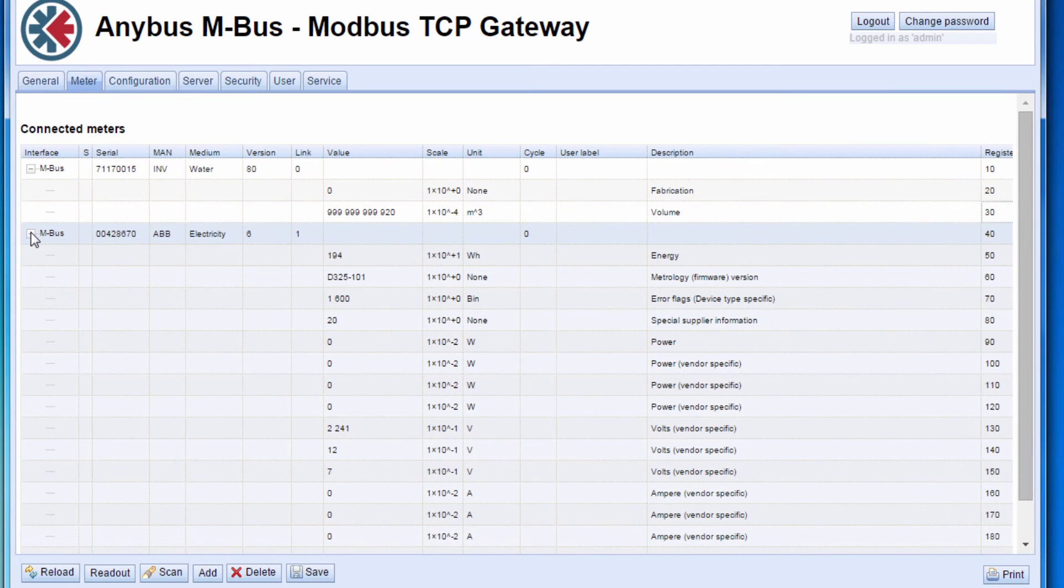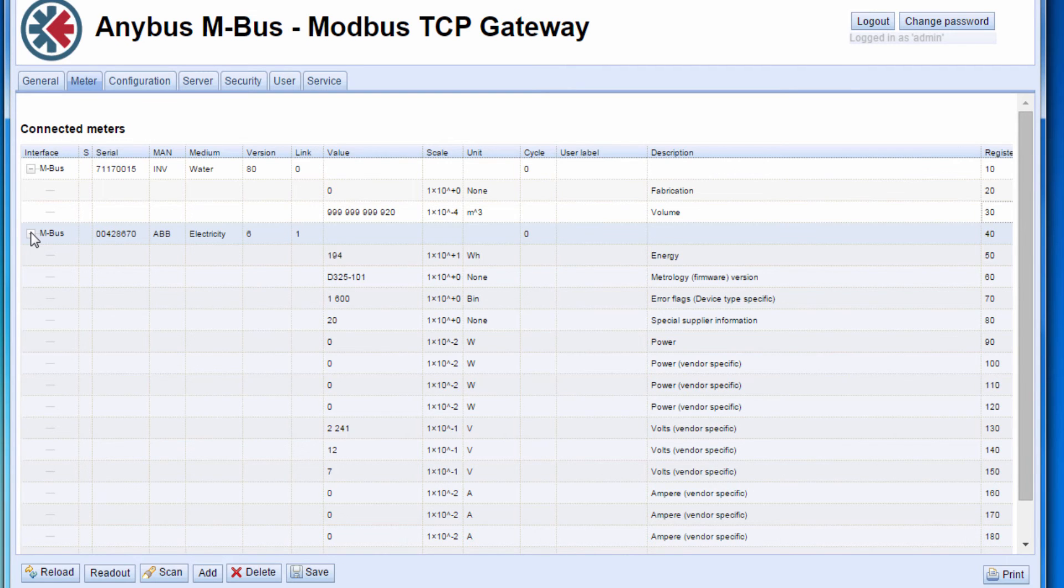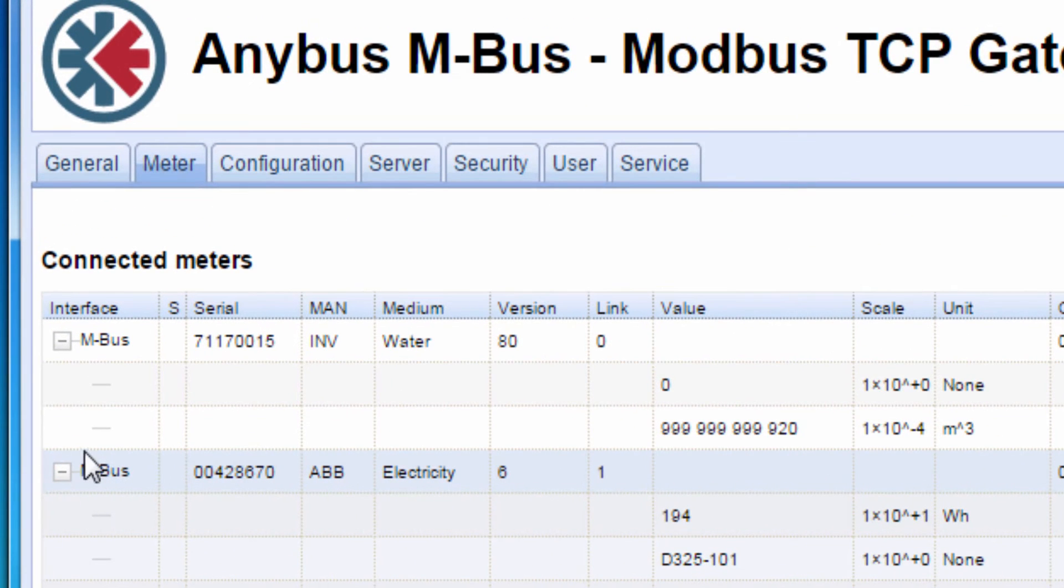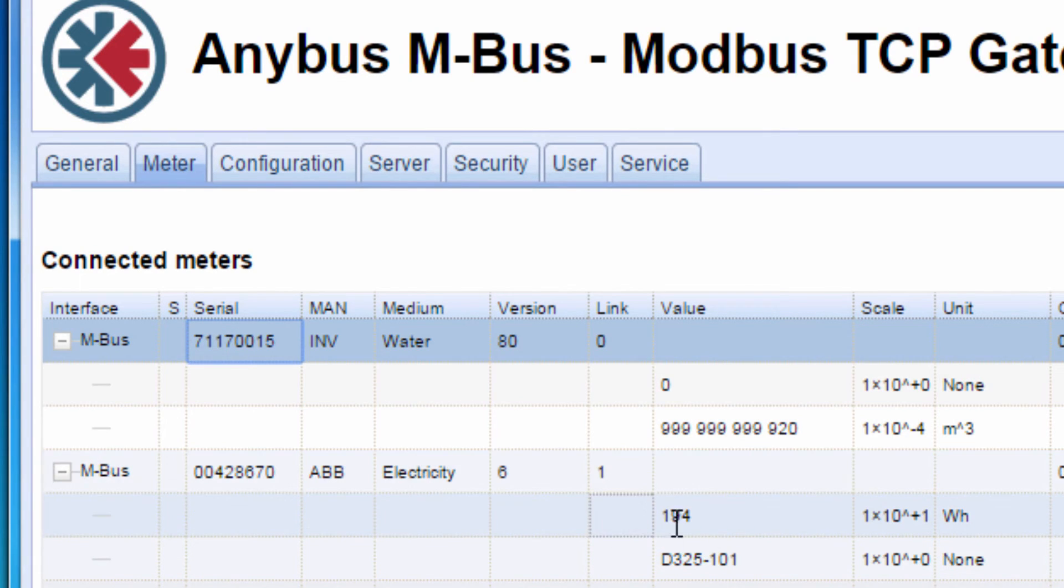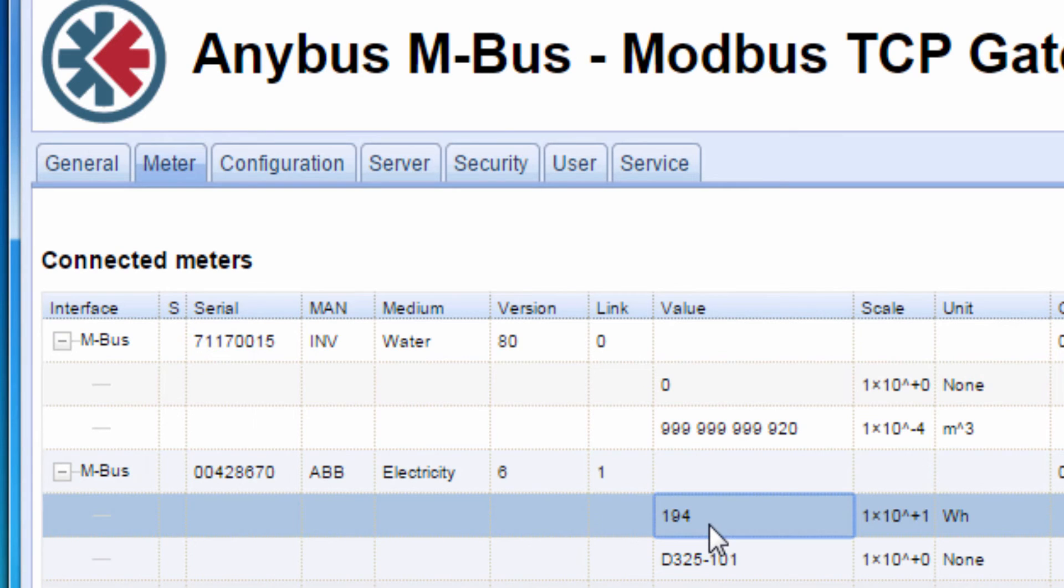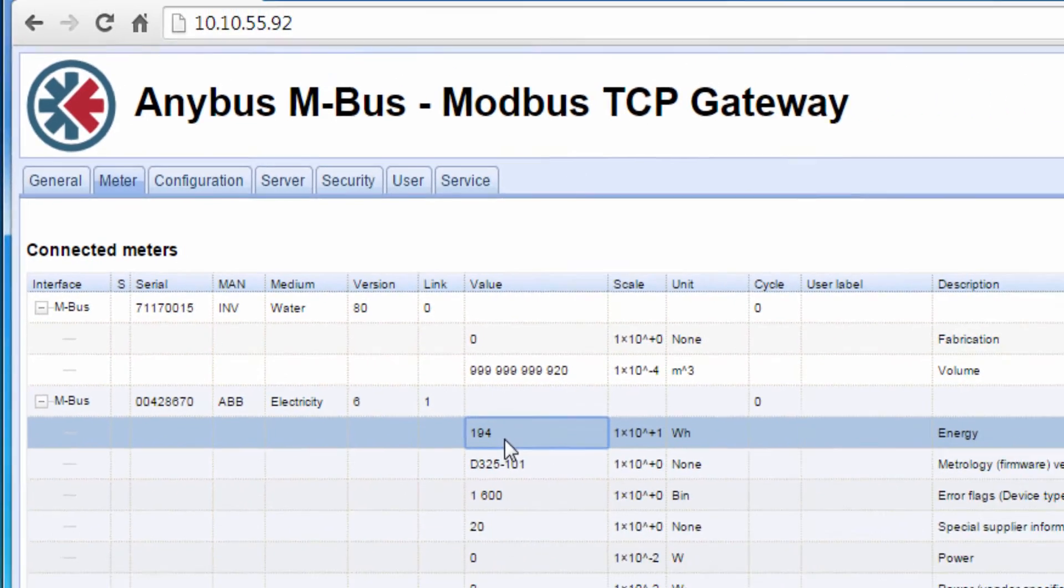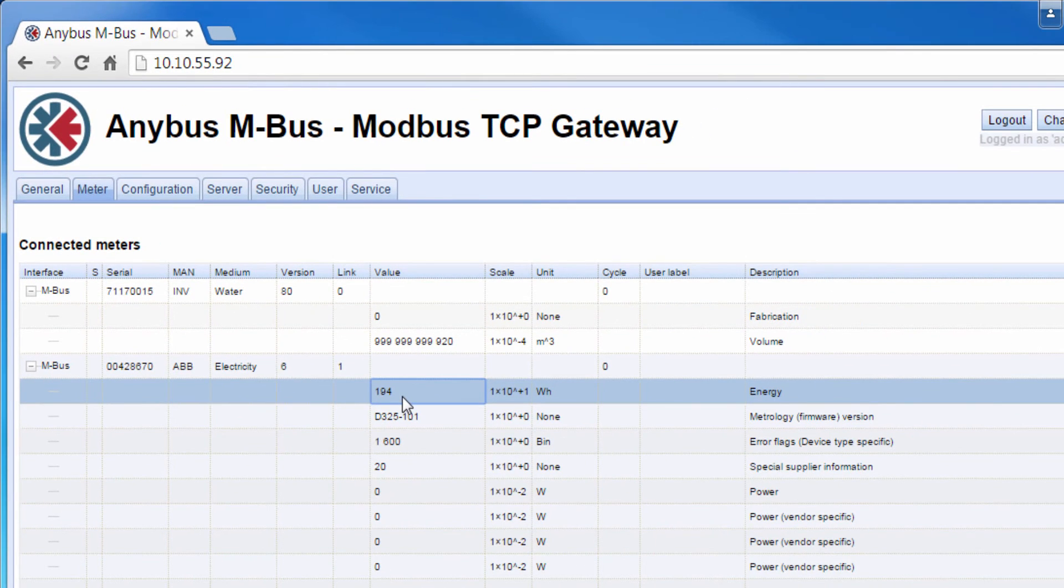For the sake of this demo, I will transfer two meter values to the Anybus X-Gateway Modbus TCP. I want to transfer serial number from the water meter, which is two Modbus registers, and the current energy value from the electricity meter, which is four Modbus registers.